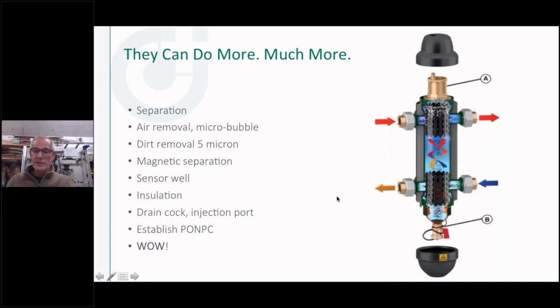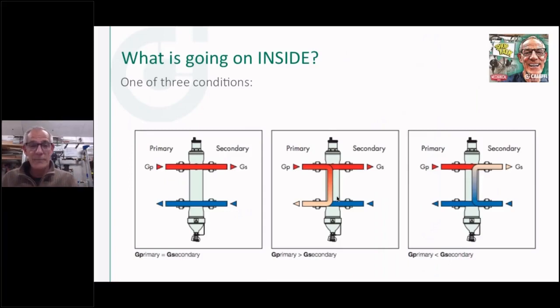So there it is. That's what we ended up with after 15 years of developing this product. We came up with what we think is an ideal device to do all this. Now, one of three things is always going to happen when a separator is flowing. If you look at the first one over here, think about this. If I've got a boiler, let's use that last example, and let's say I've got 40 gallons a minute flowing from my boiler through the hydro separator and back out to the boiler.